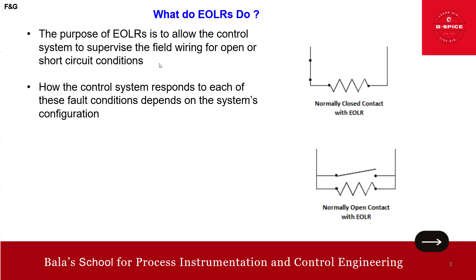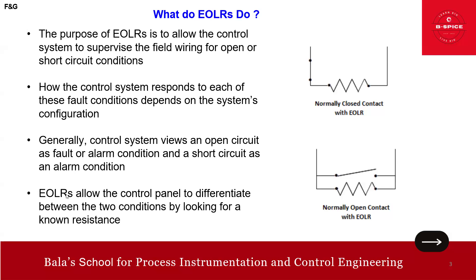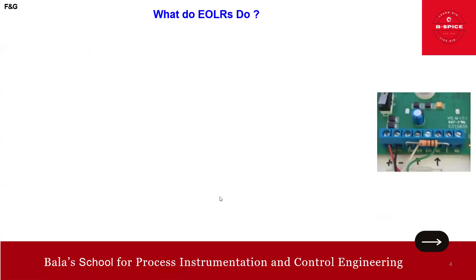The key point is that EOLR allows the control system to supervise field wiring, and how the system responds to each fault condition depends on configuration. Generally, the control system views an open circuit as a fault or alarm condition, and a short circuit as an alarm condition. EOLR allows the control panel to differentiate between these two conditions by looking for a known resistance.